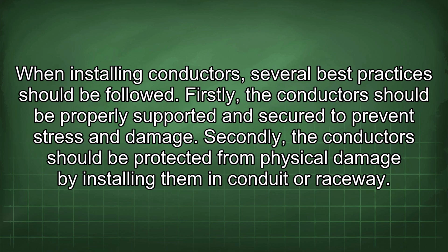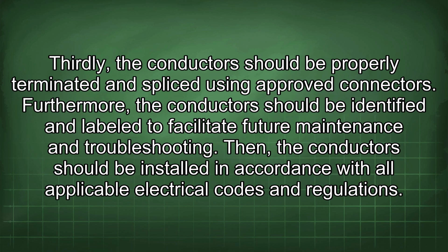When installing conductors, several best practices should be followed. Firstly, the conductor should be properly supported and secured to prevent stress and damage. Secondly, the conductors should be protected from physical damage by installing them in conduit or raceway. Thirdly, the conductors should be properly terminated and spliced using approved connectors. Furthermore, the conductor should be identified and labeled to facilitate future maintenance and troubleshooting. Then, the conductors should be installed in accordance with all applicable electrical codes and regulations.